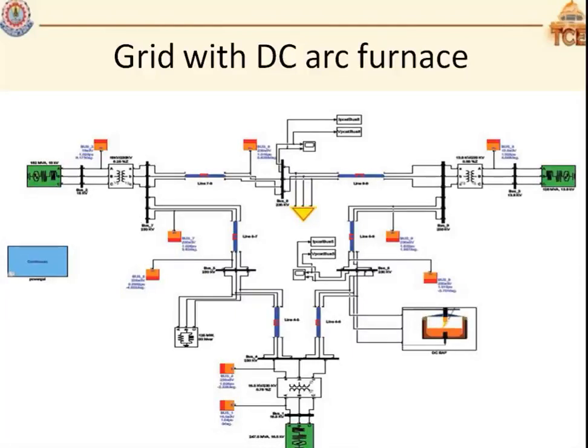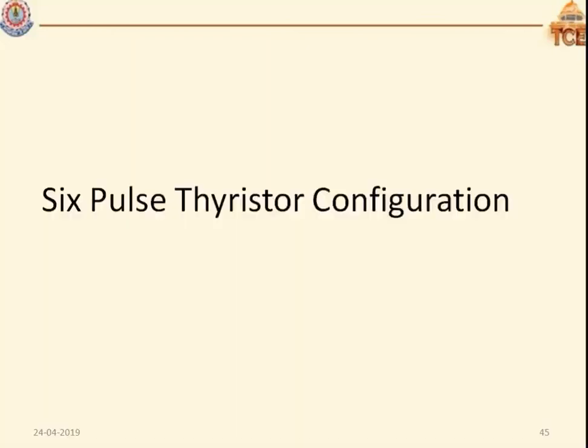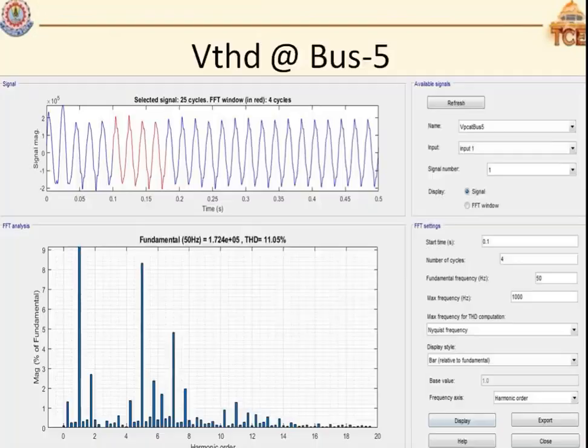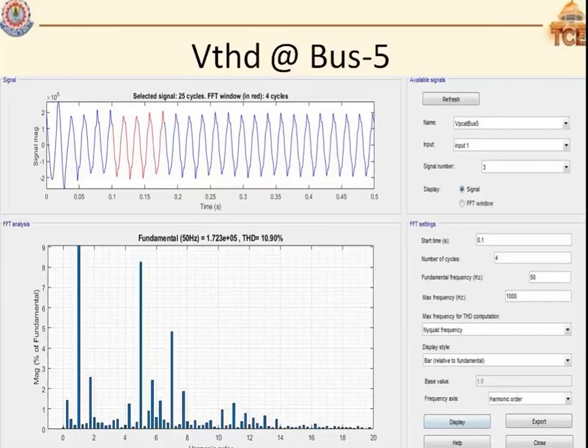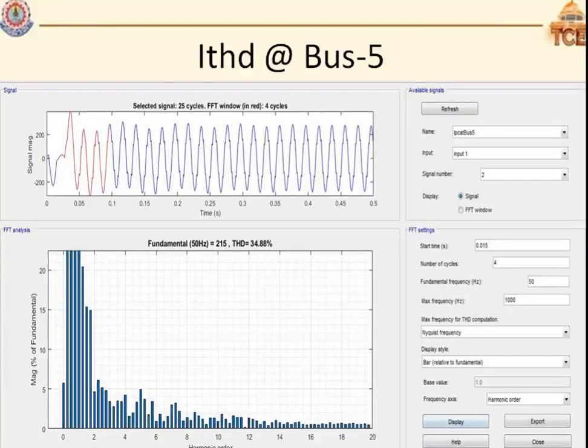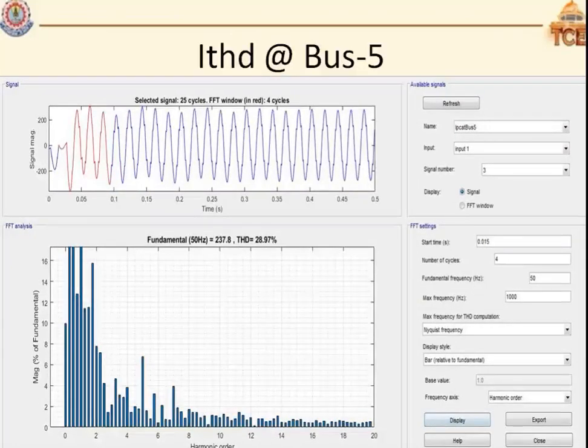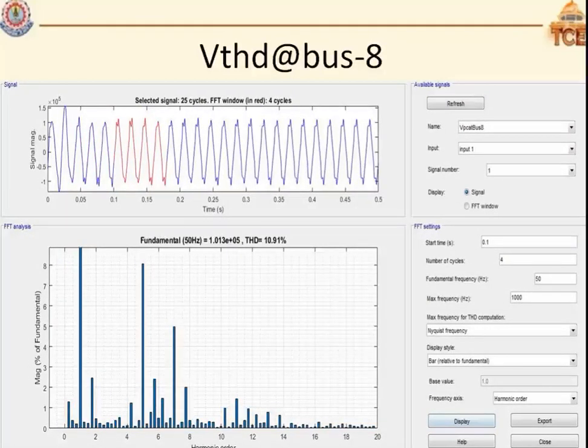Next, the grid with the DC arc furnace, which we are going to validate. First, we implement the conventional thyristor based topology, which is a 6 pulse converter topology. With the 6 pulse converter, we place the DC arc furnace at bus 5, and the voltage THD at bus 5 is about 11.05% for all the phases, and the current THD is around 34%. This is bus 8.